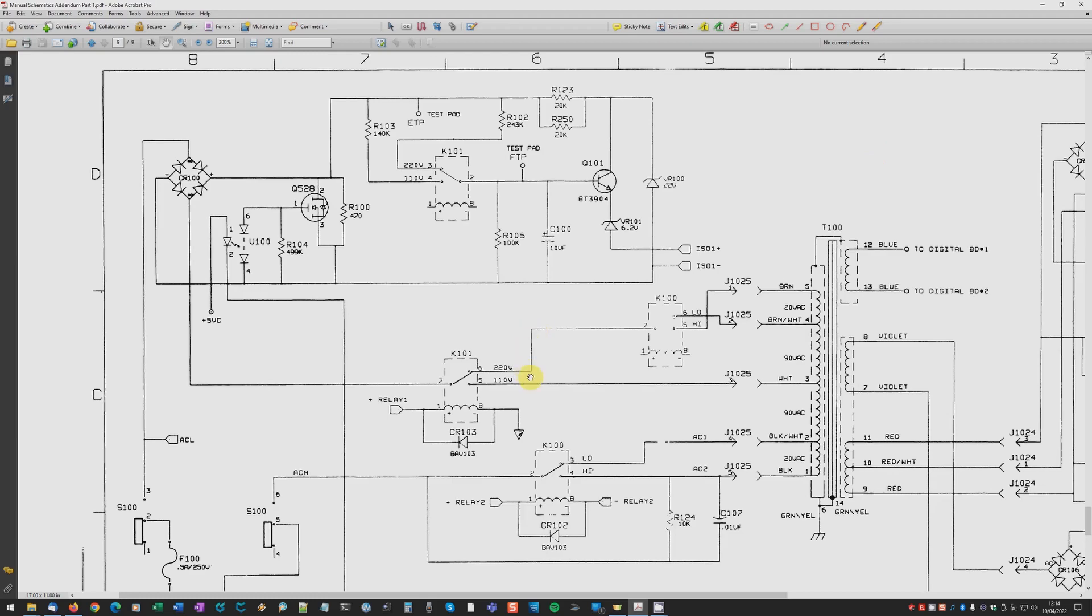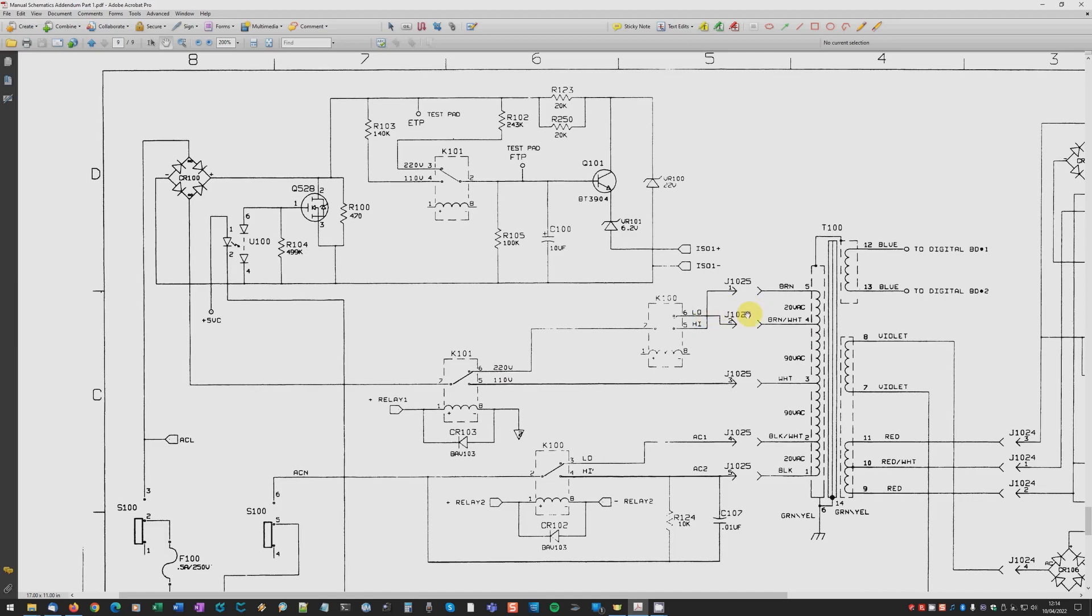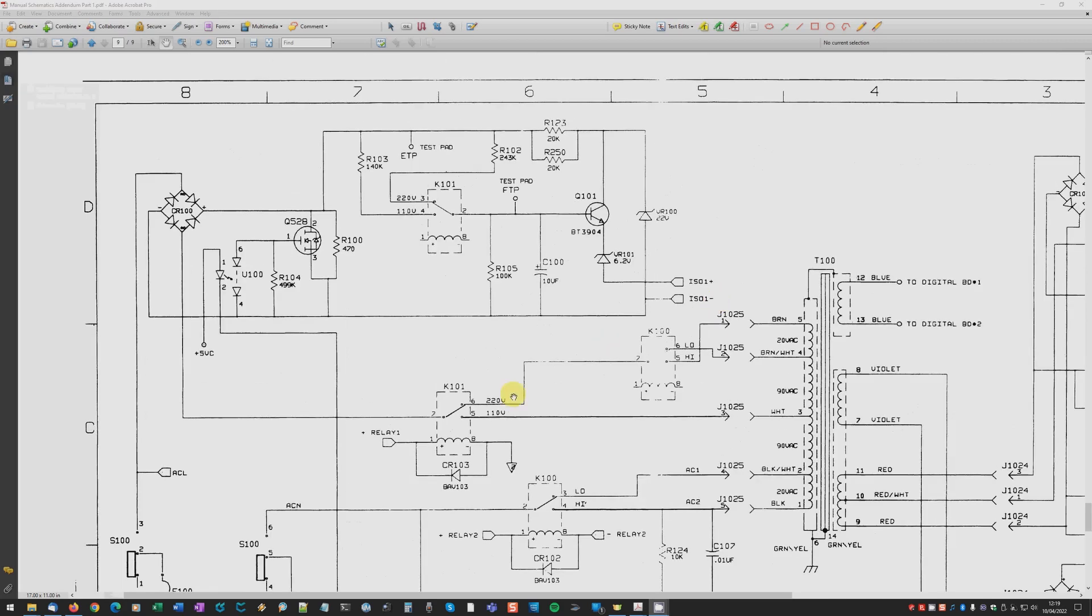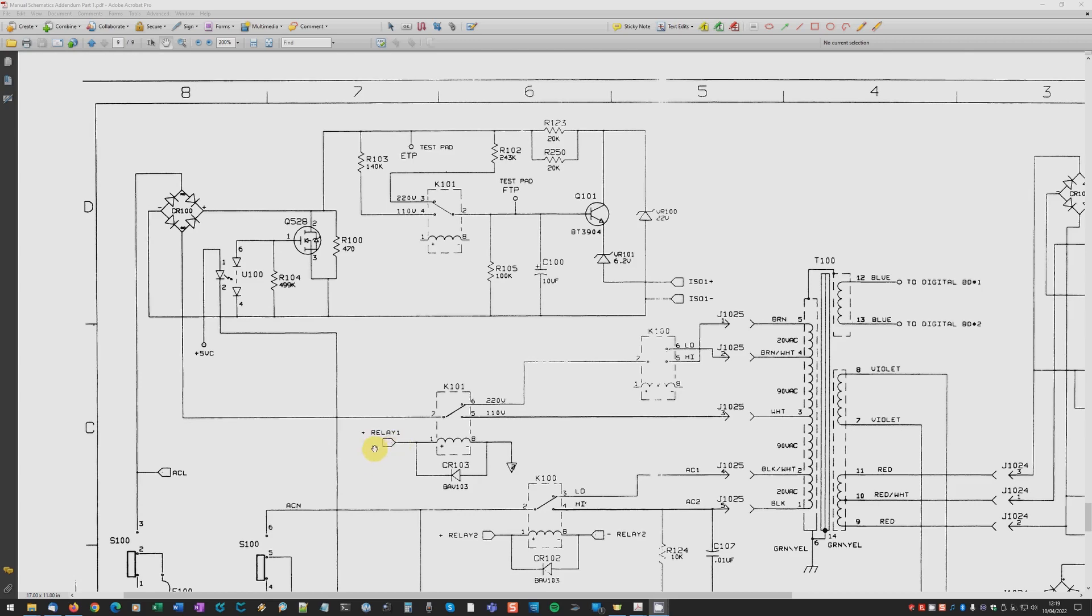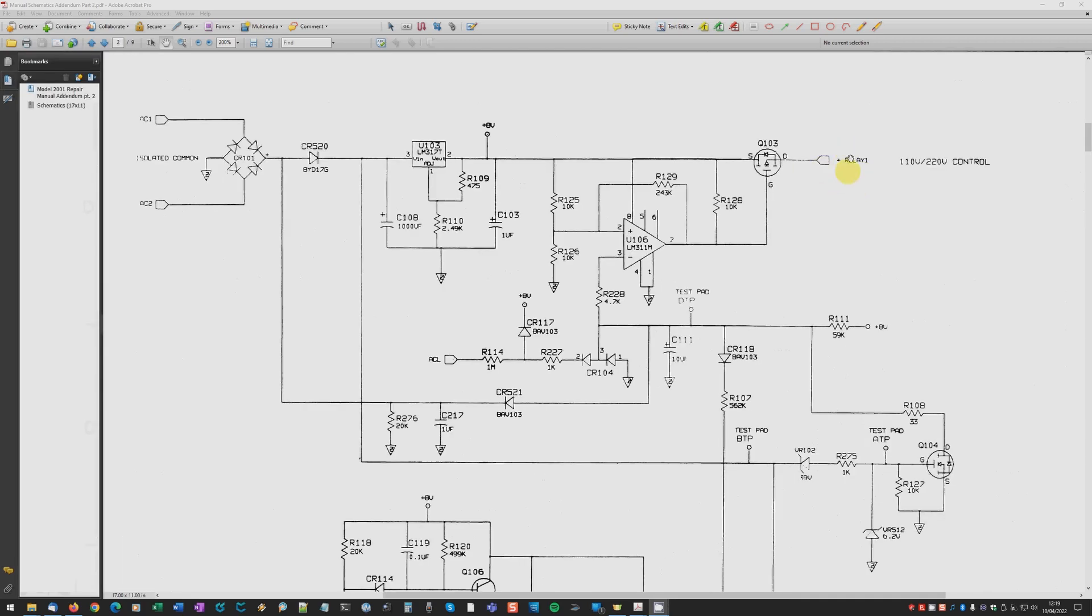Now we also have some relays here. Basically one of them takes care of the 220/110 volt selection, selecting different taps on that primary winding. You've also got a high/low control relay here, and I think that's just used to enable the extra turns required going from 220 to 240 volts. The relay here, the main relay involved, is driven from positive relay one and the other side of the coil is grounded. Let's take a look at where this signal comes from.